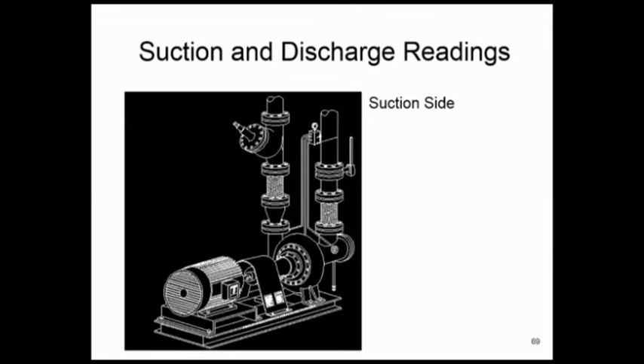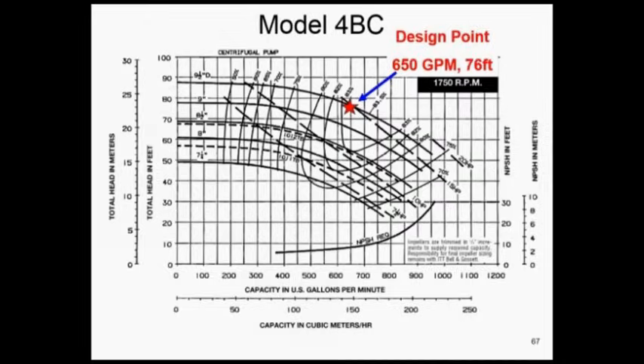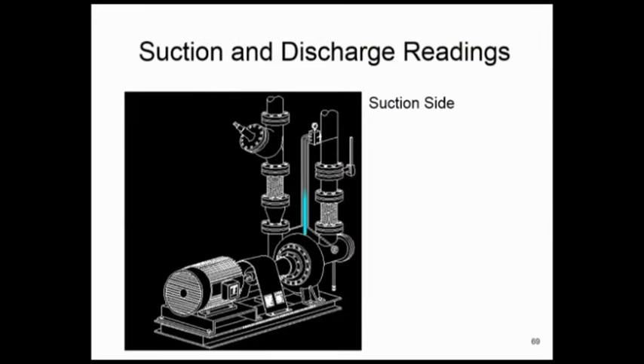What is it generating? So if I go to this thing and I look at the suction side, and I look at the discharge side, I'm coming up, our pump is generating 63 feet of head. I took the same gauge, it was in PSI, and I divided by 2.31 feet per pound, and I see my pump's generating a differential pressure between the suction side and the discharge side of 63 feet. And the specification was for what? 76 feet. See the 76? But I'm only doing 63. Now what does that mean?